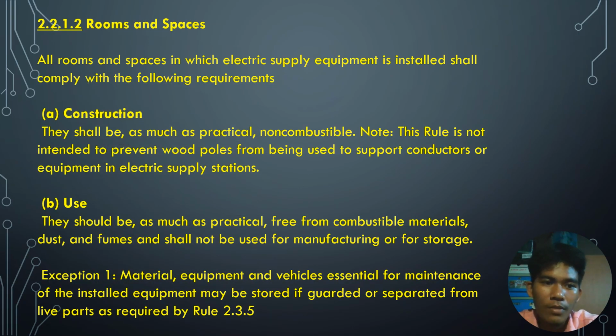Rooms and spaces. All rooms and spaces in which electrical supply equipment is installed shall comply with the following requirements. Construction. They shall be, as much as practical, non-combustible. This rule is not intended to prevent wood poles from being used to support conductors or equipment in electric supply.